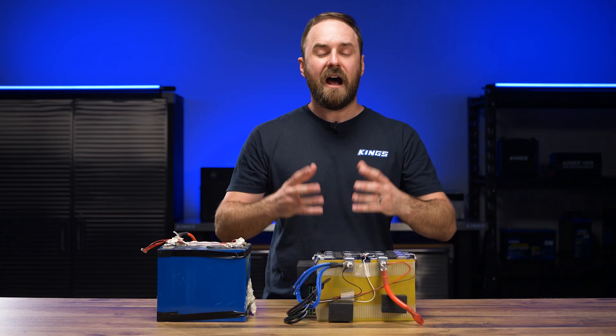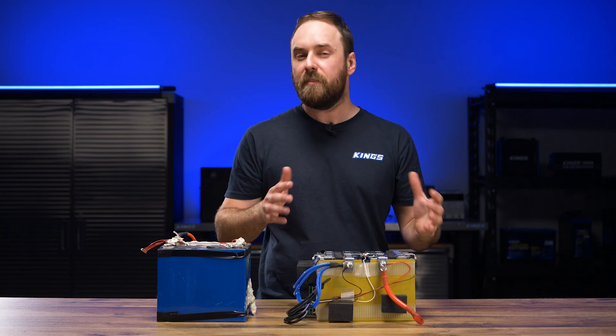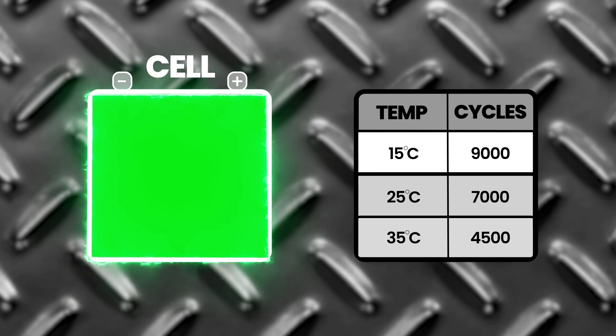As an example of how life can be affected by temperature, you'd want to keep your lithium iron phosphate cells below about 40 degrees Celsius. In one study, the same cell when fully discharged and charged over and over at 15 degrees, 25 degrees and 35 degrees Celsius respectively, was able to perform about 9,000, 7,000 and 4,500 cycles. So keeping your battery temperature down can make a big difference to overall life — and you'd want to know how your secondhand battery has been treated. It might have been overcharged and therefore overheated, or it might have been used in extreme temperatures.